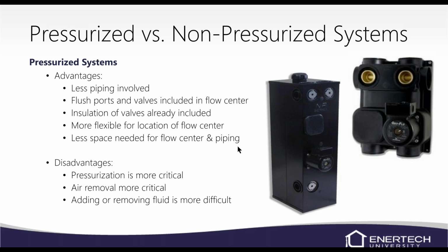There's more flexible location for mounting of the flow center. You can actually mount that flow center on the side of the unit. Matter of fact, we sell a compact, or the YT unit, sorry, the packaged unit. We have it available with a flow center that does mount to the side, on one of the doors on the lower portion of the unit. You can order it with the flow center already with the unit itself. That's the only unit we have like that.